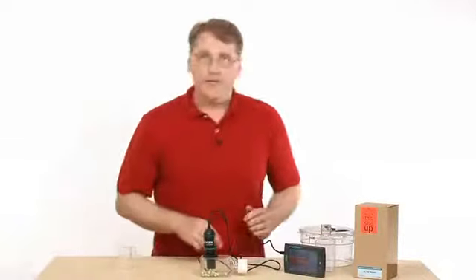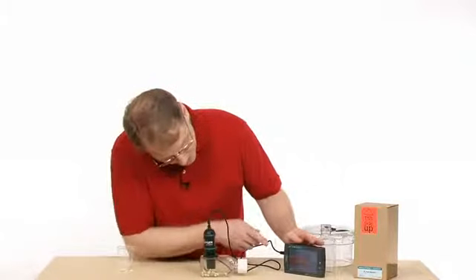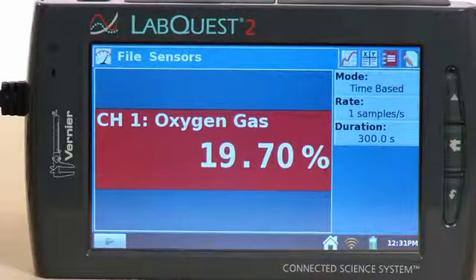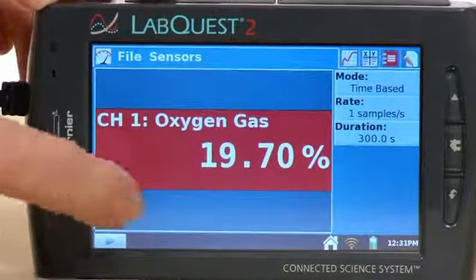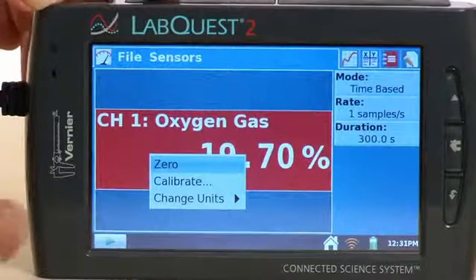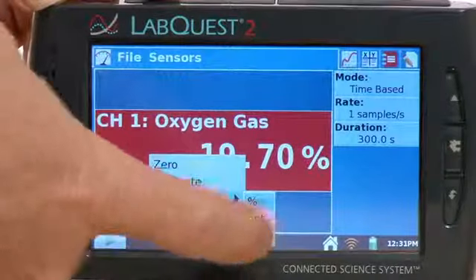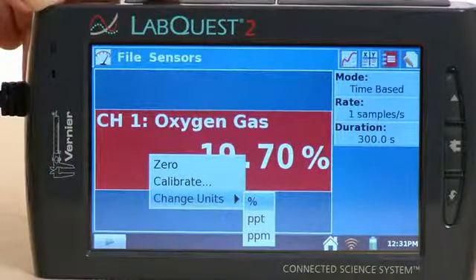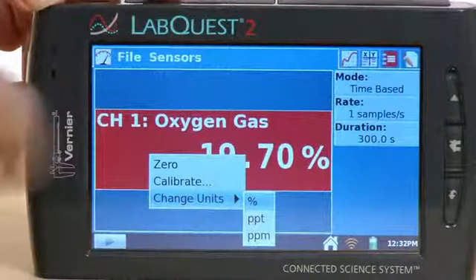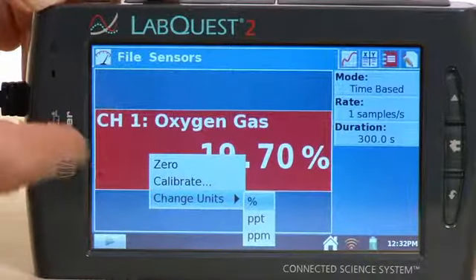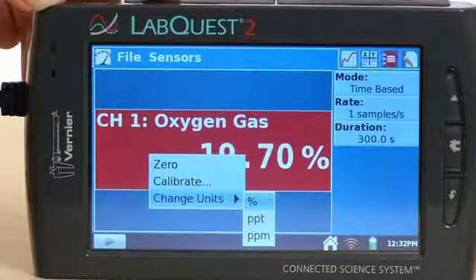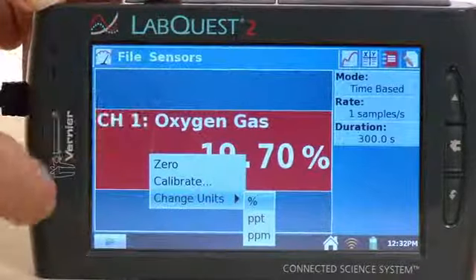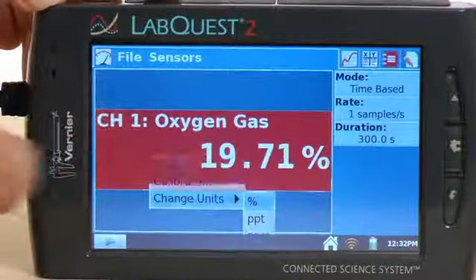And so when I do this, it's plugged into channel 1 there, so it's giving me the oxygen right now in terms of percent. If you wanted to change those units, it's easy to do. You tap on the meter itself. You can go and do change units if you would like, so I could do parts per thousand, parts per million, or percent. I'll just leave it just like it is here. We have another option there. You can zero it, so you could have it read just the change in the oxygen value if you wanted to. Or the calibration that you possibly could do if you wanted to, but we'll just leave that just the way it is.